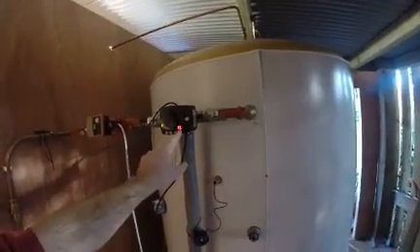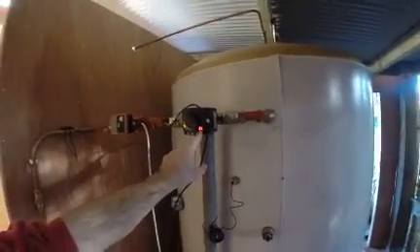It's going into the house at 78 degrees — being pumped in via an underground pipe. You can also see the top of the tank here is measuring around 70 degrees, and so is the bottom. So the buffer tank is full the whole way down with water at 70 degrees.